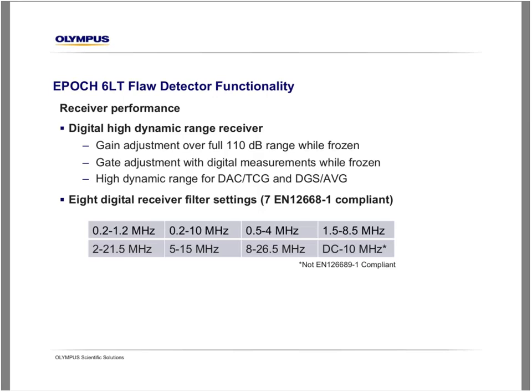And that includes a filter that we call our DC to 10 megahertz filter, which has a very low frequency component to it, essentially no high pass filter applied. This means that for thicker materials, for composite materials, for highly attenuating and scattering materials that require low frequency transducers, we have very strong capabilities to accommodate the requirements of those applications.